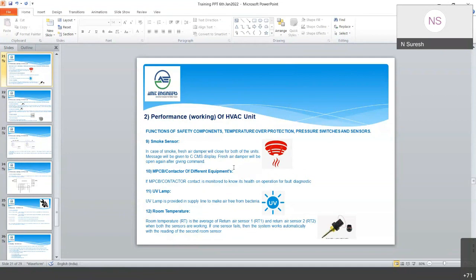In case of smoke, the fresh air dampers will close for both the units. Okay. Sir, it is assumed that the fresh air smoke detector detects the smoke outside of the compartment. Correct, sir. Vice versa, if there is smoke inside of the compartment, then whether fresh air intake is continued or stopped. No, sir. Here, in fact, we are supplying the complete smoke detection system in this project, and inside the coach there are systems available where air samples are continuously taken into the system, and if there is any smoke inside the coach, there will be a command to the TCMS. In turn, the TCMS will give a command to switch on or off all the subsystems.